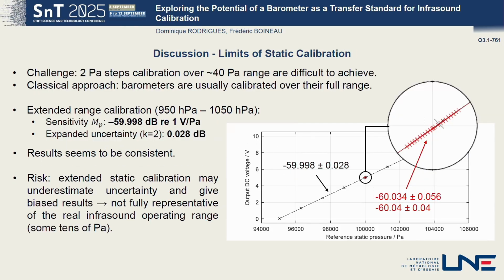Just before concluding, I would like to discuss some extra information regarding a potential limit of the static calibration. Calibrating a barometer with 2 Pascal steps over a 40 Pascal amplitude is very challenging, and this is not a classical, usual calibration service provided by the static pressure labs. The usual approach is instead to calibrate the barometer over its full range. This is why, when we buy a new barometer, or if you ask for a usual calibration service, you will obtain this kind of result. So we did it here also. We asked the static pressure lab to calibrate the same barometer but in the full range with a classical approach.